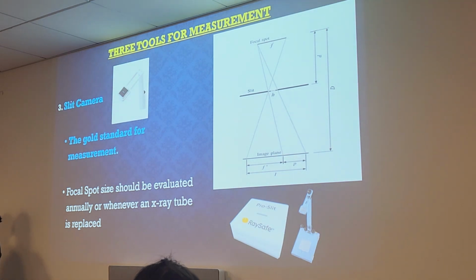And you'll extend it over the IR, you have your tube above, and the medical physicist will measure at a parallel angle with one exposure, and a perpendicular angle at another exposure. That's how they measure the focal spot size. I don't know the calculations, every calculation is different. This is just basically how they use the slit camera to measure focal spot size, or one of the ways they measure it. But guess what all you need to know from this slide?